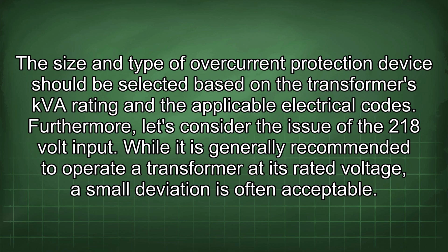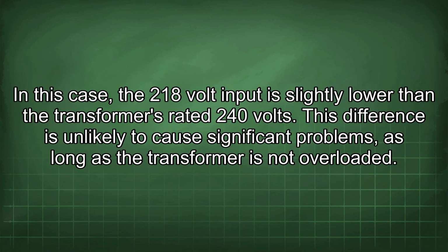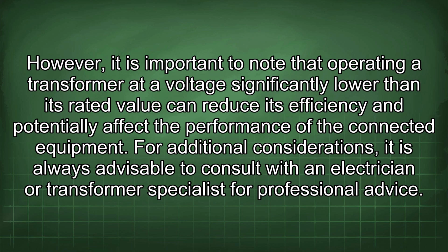While it is generally recommended to operate a transformer at its rated voltage, a small deviation is often acceptable. In this case, the 218-volt input is slightly lower than the transformer's rated 240 volts. This difference is unlikely to cause significant problems as long as the transformer is not overloaded. However, it is important to note that operating a transformer at a voltage significantly lower than its rated value can reduce its efficiency and potentially affect the performance of the connected equipment.